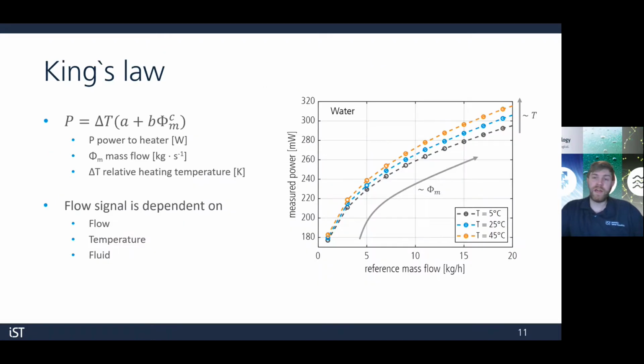With the anemometric principle, we rely on King's law. Here's a simplified version of the equation, which is explained a bit further in our application note. It gives us the power which is delivered to our heater for different flow rates. As you can see with the water example on the right, the curve is dependent on our liquid temperature, the flow behavior of the liquid, and the liquid type. So here we can see the temperature of our liquid at 5, 25, and 45 degrees C. And you can see how the sensitivity is slightly different for each, and the curve follows a different profile.